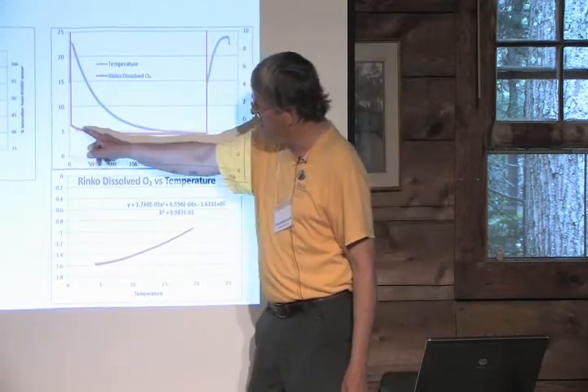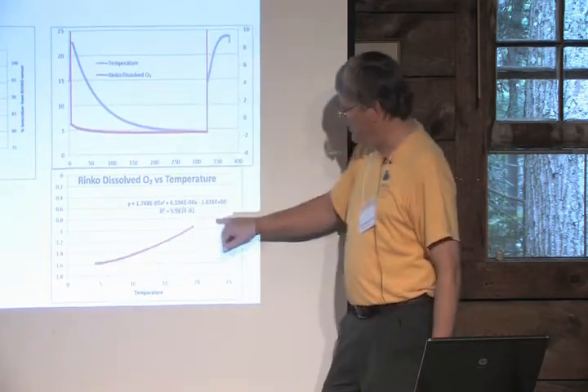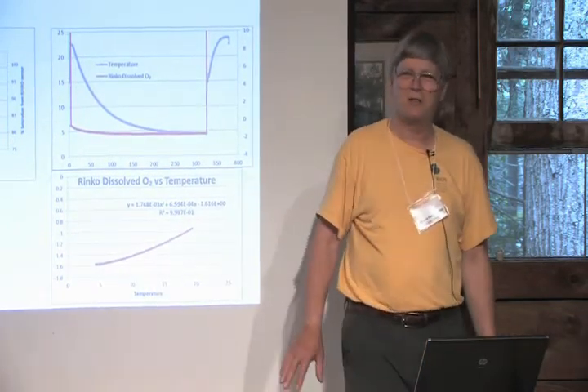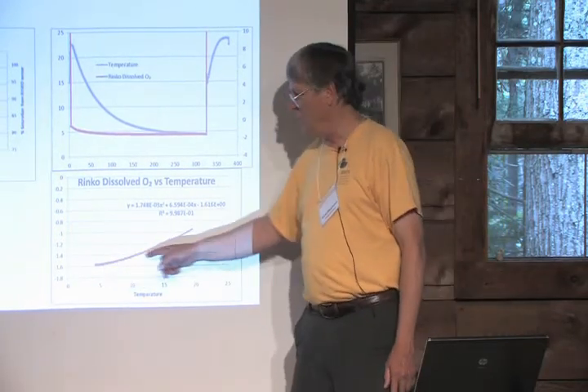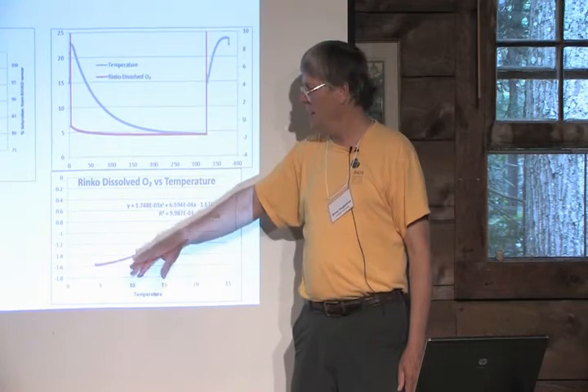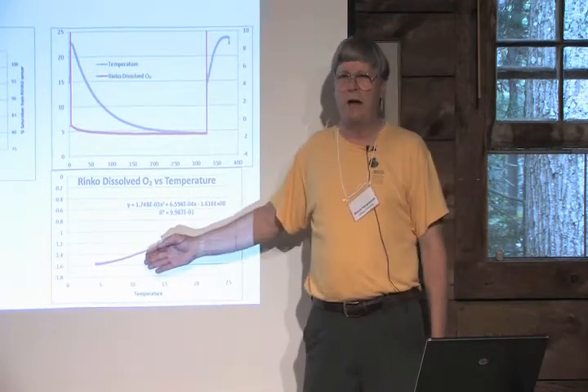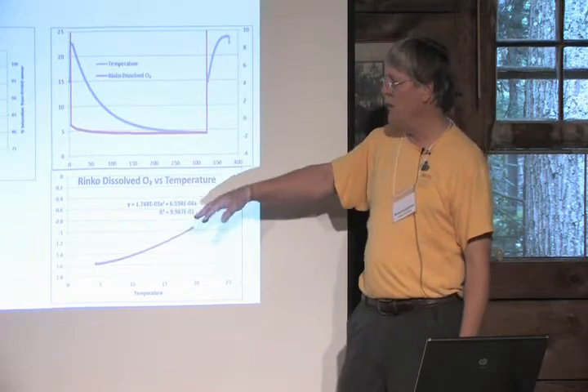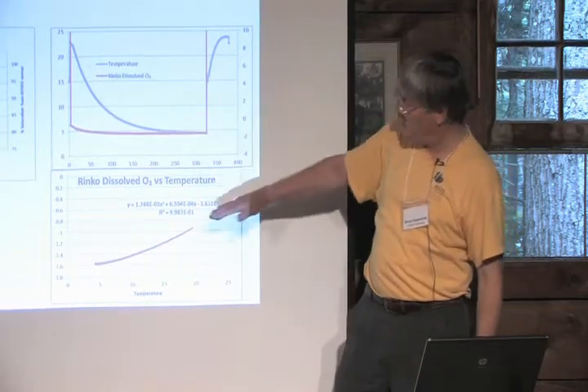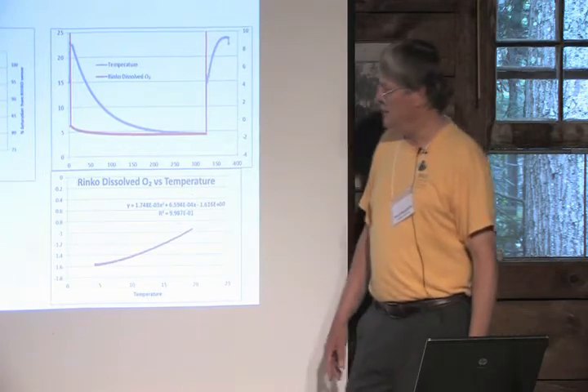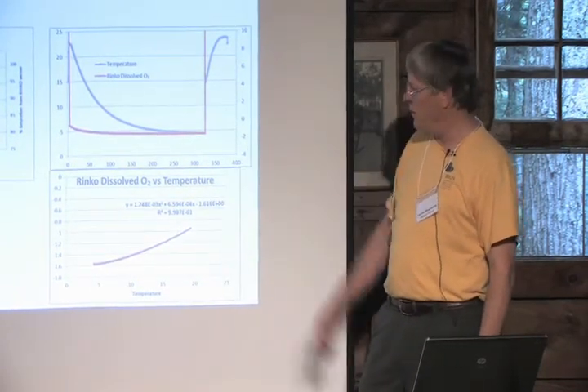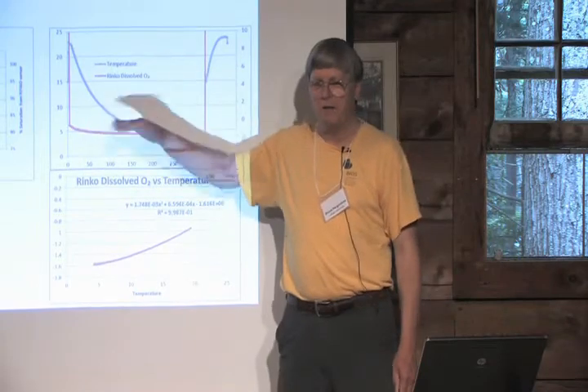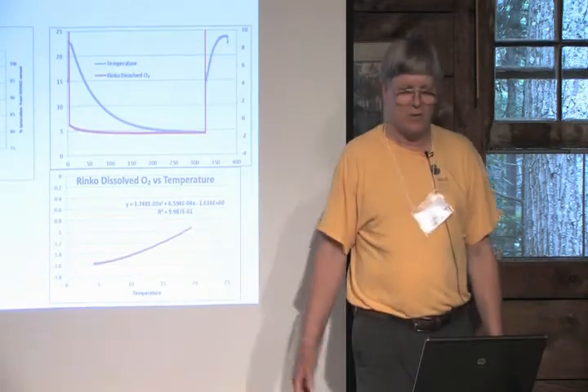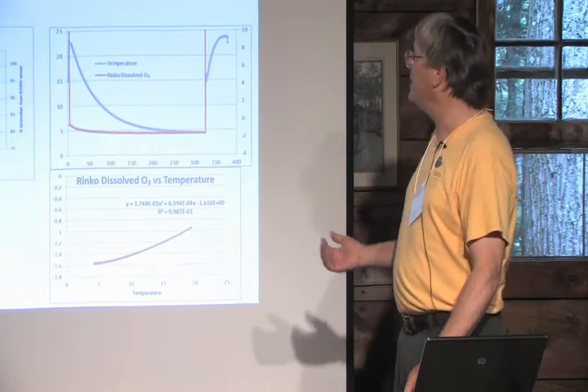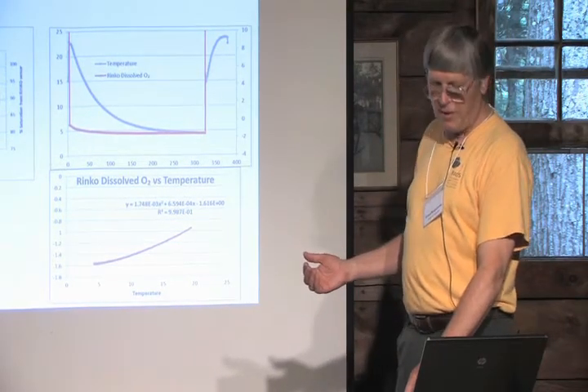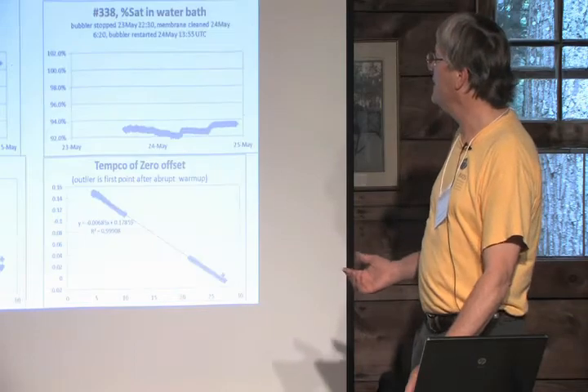And when you plot this curve versus temperature, we get offset versus temperature. This is very useful if you're working at low oxygen, because now you can say, I know what my temperature was. I can subtract this amount from the recorded signal and get a much more accurate signal at low oxygen. This will also have a slight effect on your high oxygen signals too, because this number is a percent out of saturation with the Rinko. So very simple. You put it in a bucket, cover it, let it cool off, record the data. It's just logging. In this case, it's logging more frequently, I think, at maybe 1 minute intervals compared to the field rate of 1 hour intervals.